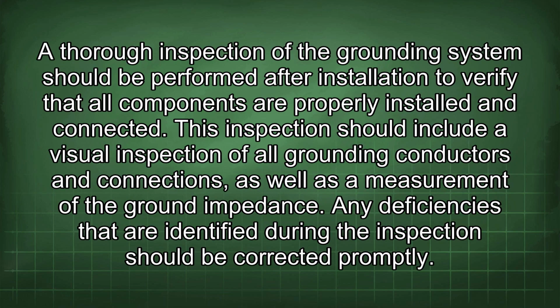A thorough inspection of the grounding system should be performed after installation to verify that all components are properly installed and connected. This inspection should include a visual inspection of all grounding conductors and connections, as well as a measurement of the ground impedance. Any deficiencies that are identified during the inspection should be corrected promptly.